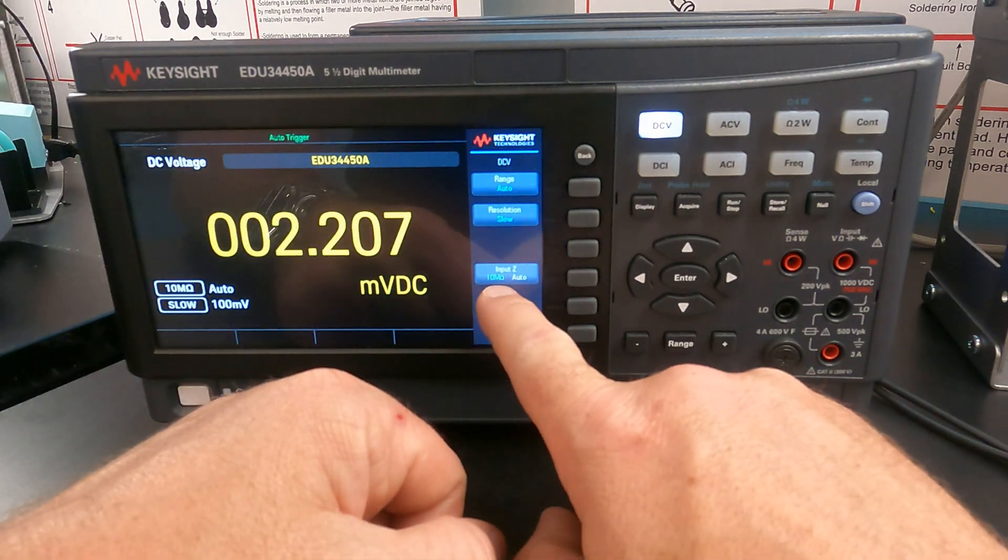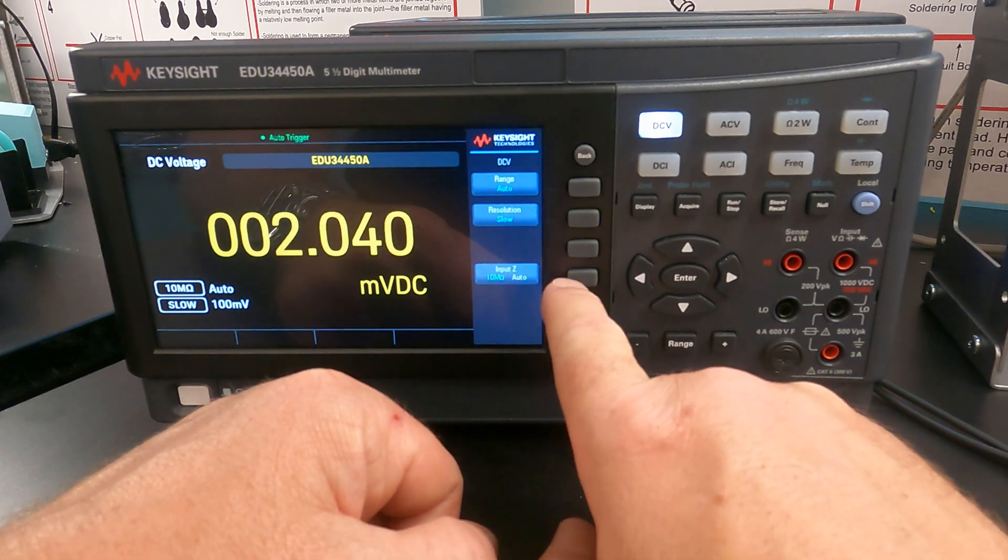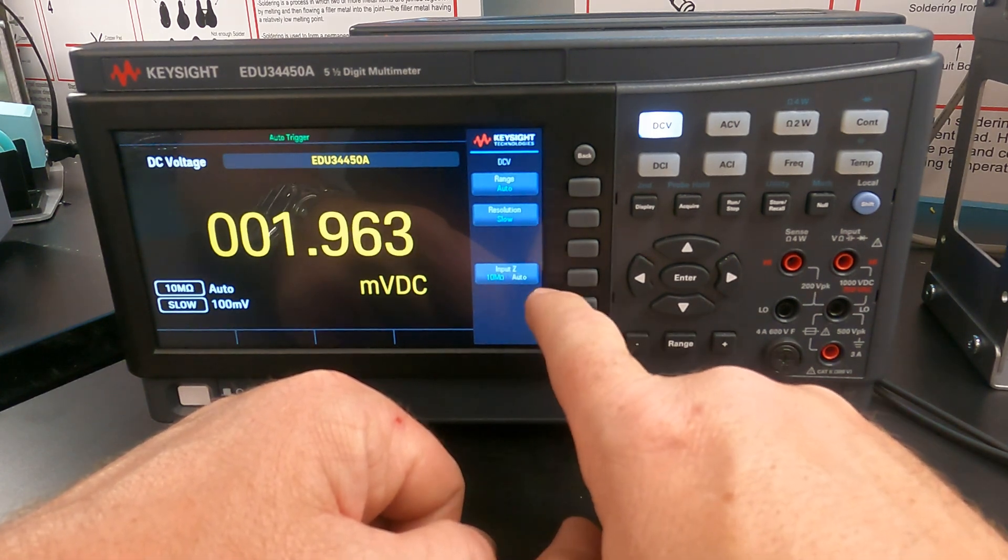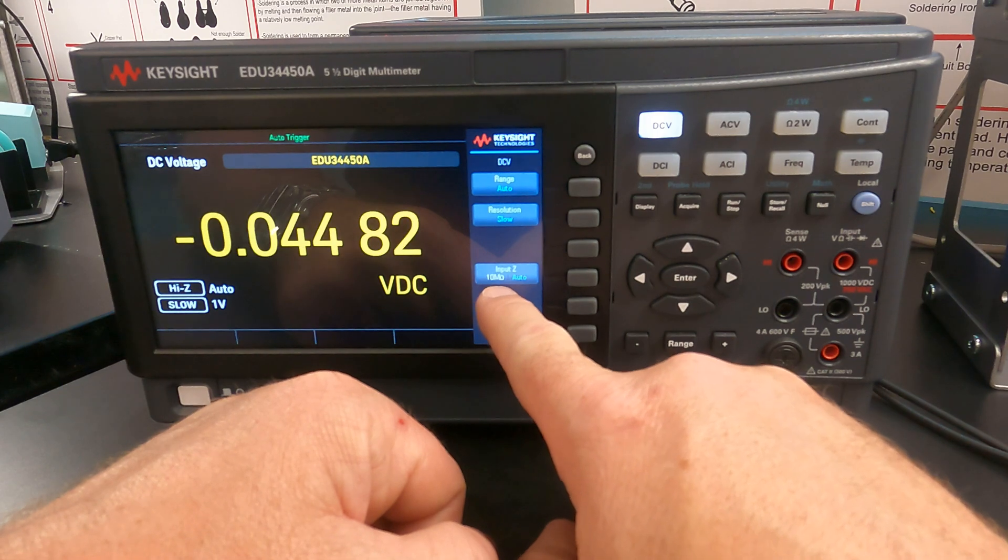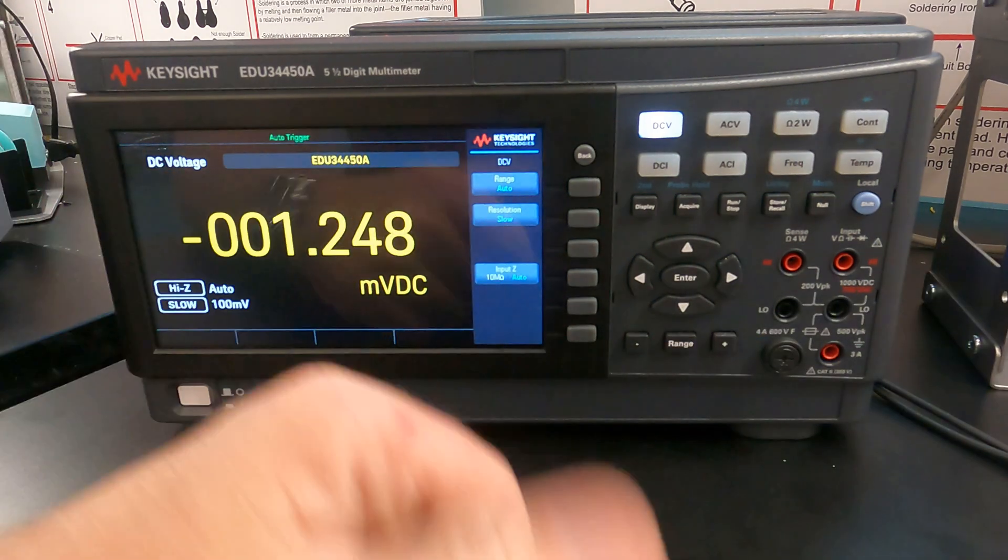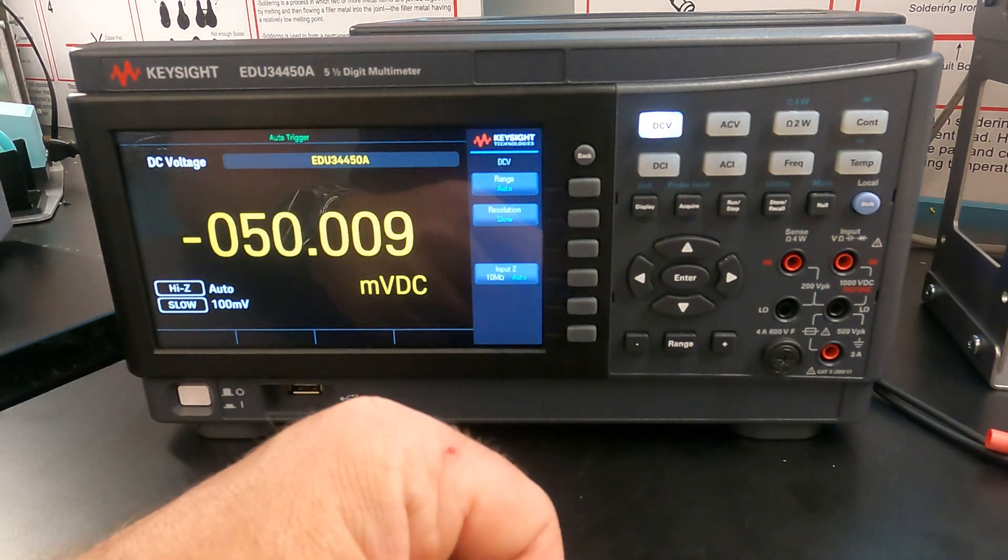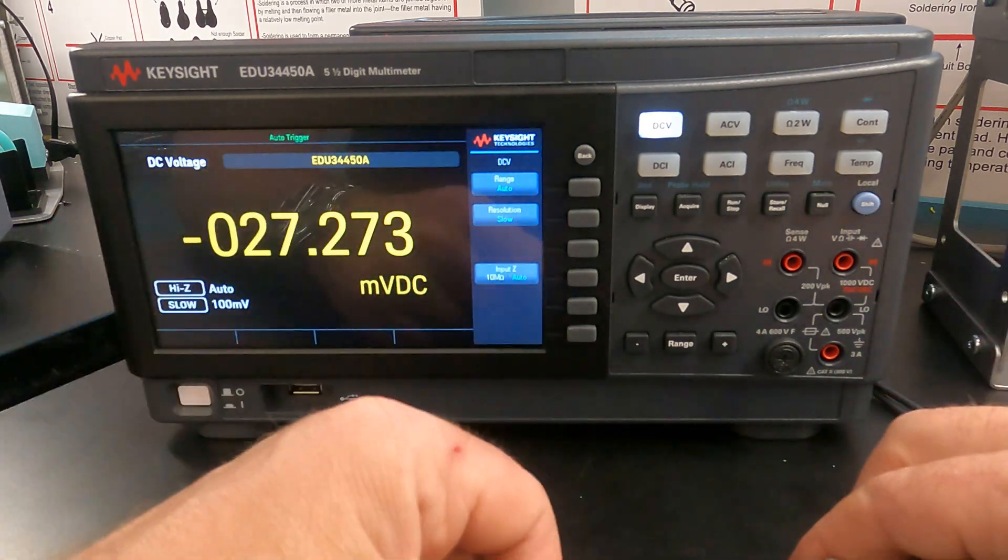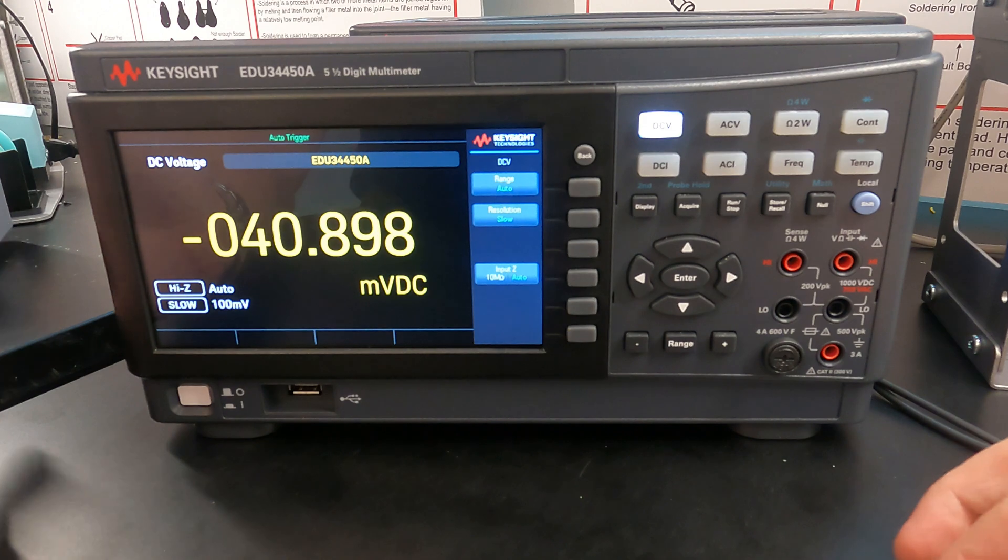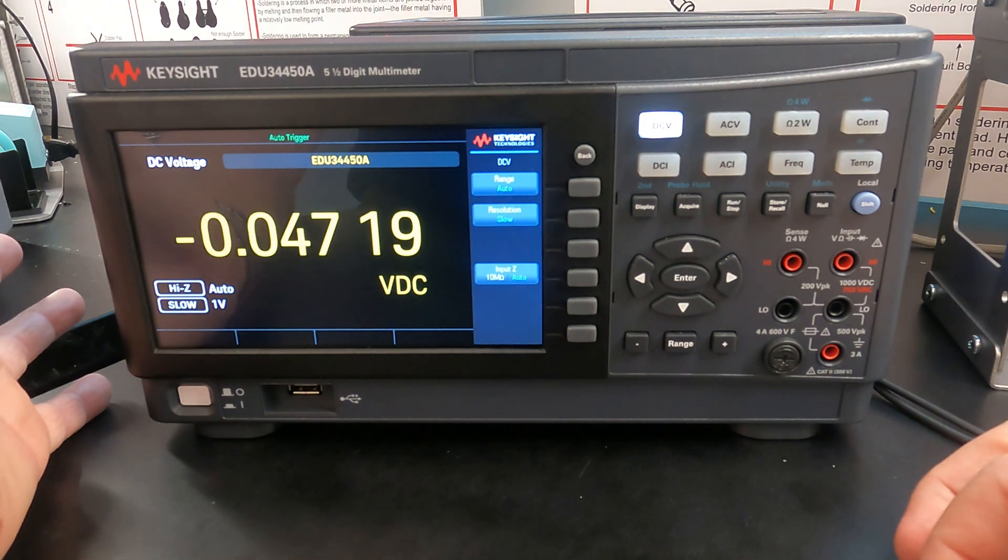And typically we want our input impedance to be high. So this is input impedance. We typically want that on auto, 10 megaohms. So that means that when we attach this to a circuit, it's going to impose about a 10 megaohm impedance on the circuit, which typically for most circuits is pretty minimal effect to the circuit.